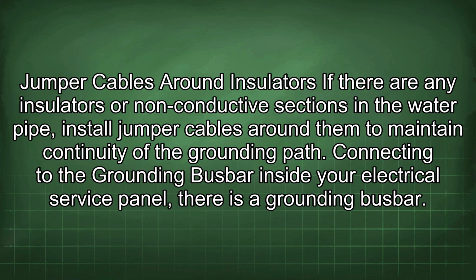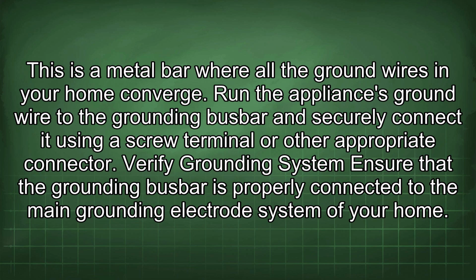Connecting to the grounding busbar. Inside your electrical service panel, there is a grounding busbar. This is a metal bar where all the ground wires in your home converge. Run the appliance's ground wire to the grounding busbar and securely connect it using a screw terminal or other appropriate connector. Verify your grounding system. Ensure that the grounding busbar is properly connected to the main grounding electrode system of your home.